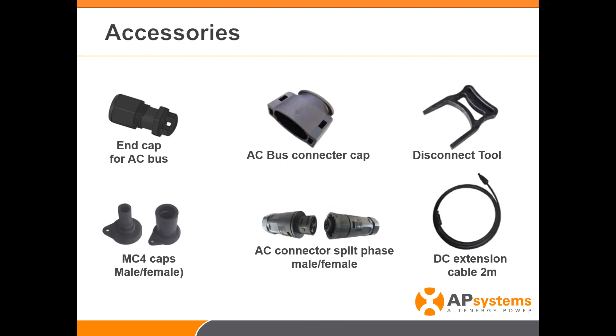So right to left, we have the end cap securing the open end of the bus cable, making it watertight again. Next, we have the microinverter. Apparently here we have an odd amount of panels, so we can use the DC caps for correct closure of the free input. The AC bus cap, as shown, can close up any free connector passing by a chimney, a tilt roof, or another obstacle on the roof. Bringing it up to the last microinverter on our bus cable, to be connected to the installation's main breaker box.